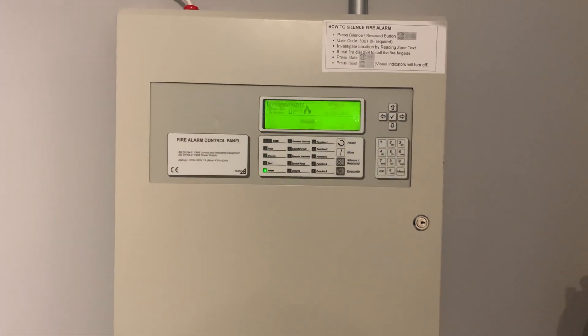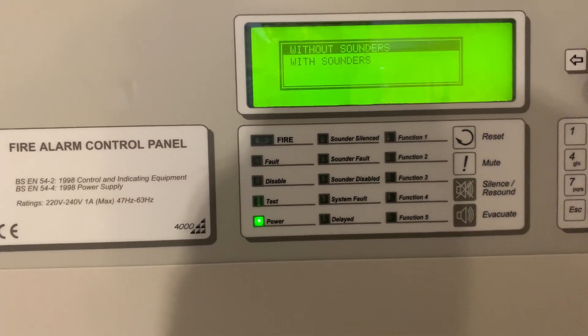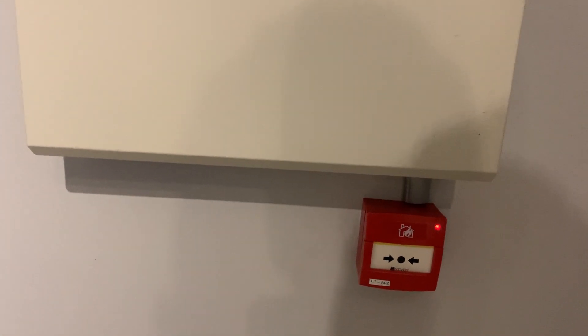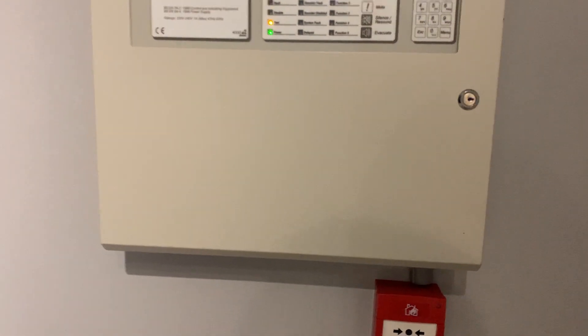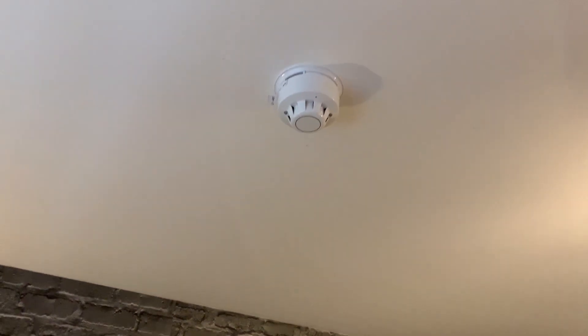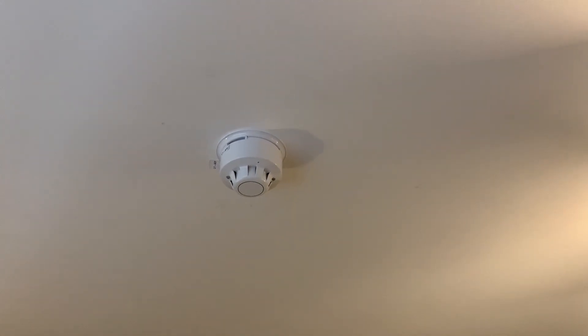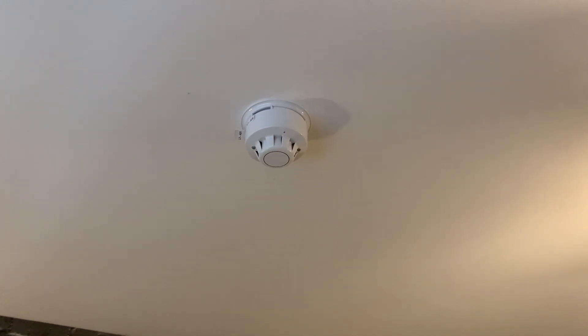It's back to normal. Now that's reset, I'm going to pop my room into test mode because we're going to test this discovery optical and this call point. For the test we want zones with sounders. Now for this optical you can see the discovery poll too — that should be loads enough. You can see this is address 16 because this was the last device, most recently added. Usually I have the detector one plus their base with most of these, apart from this one.